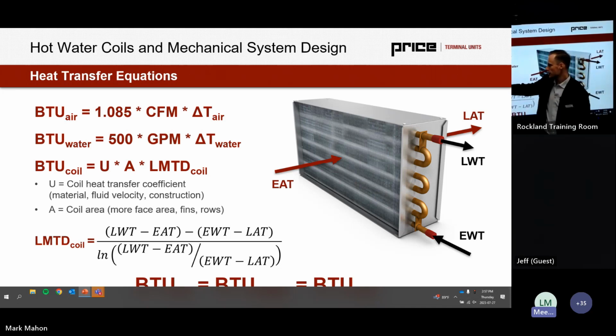And so the capacity is equal to the log mean temperature difference of the coil times two different coefficients. The first is the coil heat transfer coefficient, which is based off of the material and the construction of the heat exchanger and the fluid velocity through the heat exchanger. So is it laminar or is it turbulent? We then also have the coil area, and this is an effective face area. So this isn't just the height and the width of the coil. This is how many fins per inch I have, the fin thickness I have, the tube spacing and the tube diameters. All of this comes out to an effective heat transfer area.